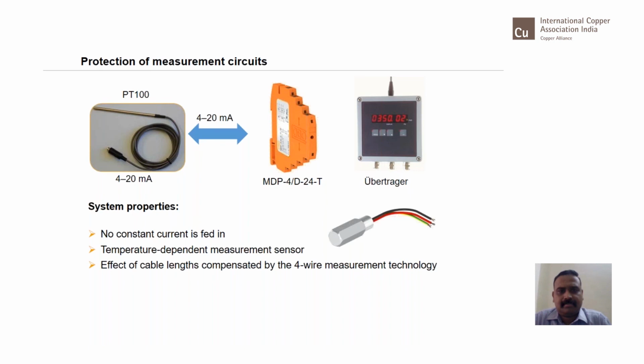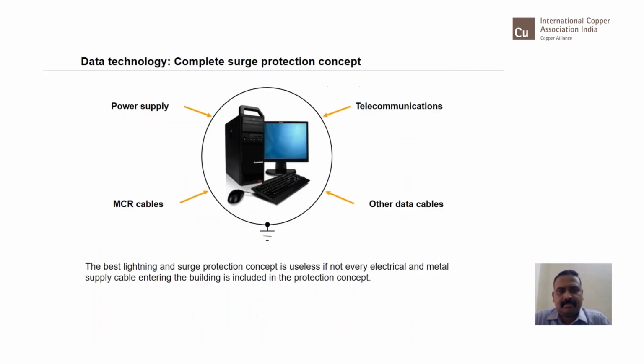The SPDs are required. So in a nutshell, if your equipment is to be protected against a surge, not just a power SPD will help you. You need to ensure that where equipment is connected with power, data, voice, and communication, all those entry points are protected with the appropriate surge protection at that location. Only then will you be able to achieve a proper total solution against lightning.